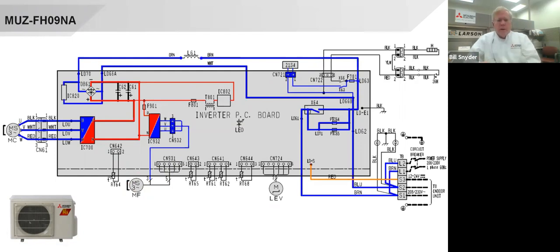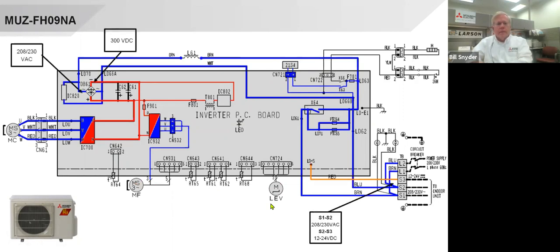In this case, we also have, these are your thermistors down here. Again, you're entering, you're leaving coil thermistor, your outdoor ambient thermistor, and your discharge thermistor off of your compressor. And this is the linear expansion valve. You can see clearly on this, that symbol, that AC and DC symbol. And you'll see the voltages all pretty much fall into play. Again, this 300 volts is a nominal 300 volts. And obviously your voltage going in is somewhere between 200 and 240 volts. So that's going to change this.